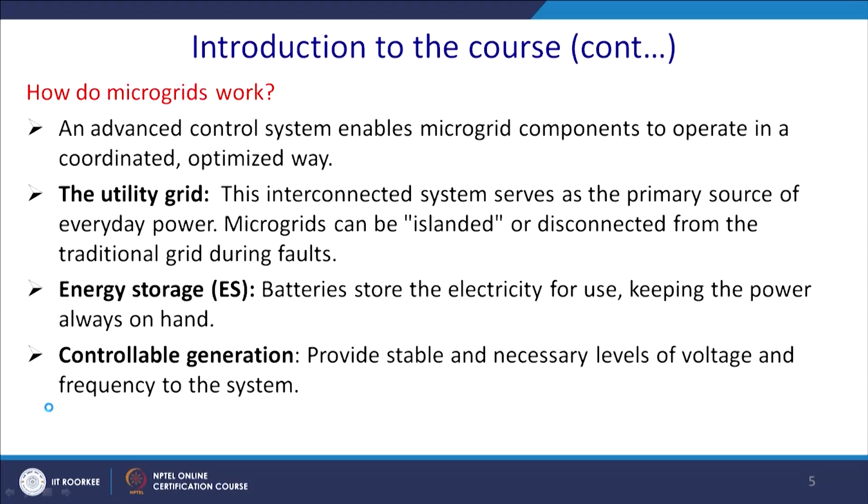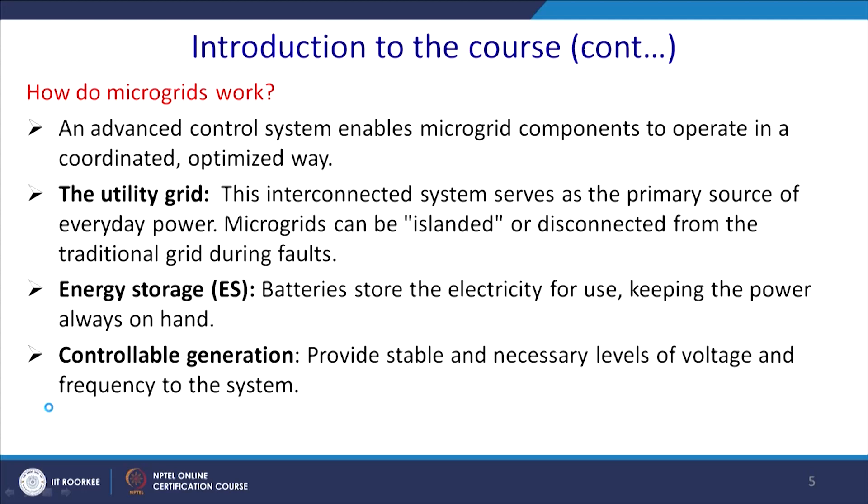The utility grid, the interconnected system, serves as the primary source of everyday power. A microgrid can be islanded or disconnected from the traditional grid during a fault. If there is a fault, you can cut your system from the traditional grid and operate with critical loads depending on available local power. Energy storage (ES) — most commonly a battery — stores electricity to keep power on hand, giving autonomy. For example, in a solar-based system, during 2 or 3 rainy days, you supply power from the storage battery. Storage power serves to meet these contingencies.